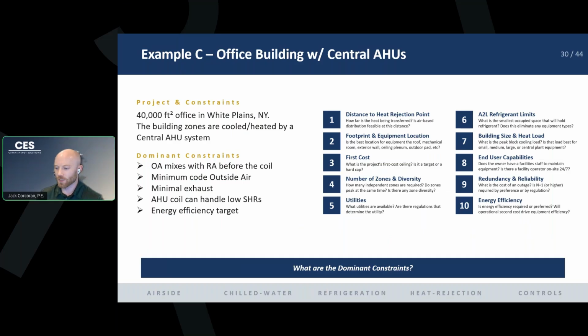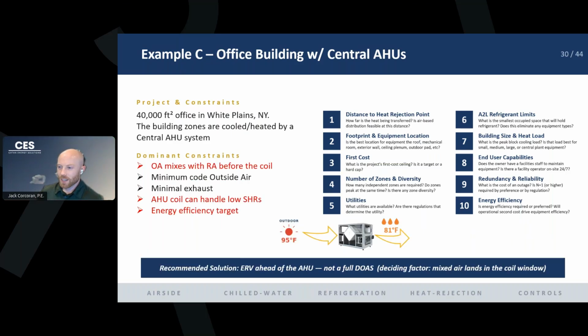And then you want to have an energy efficient system. This owner wants to hit a target. So what outside air system are we going to use here? Let's use an ERV, right? We don't have a huge latent load in our space, and the outside air is going to mix with the return air.